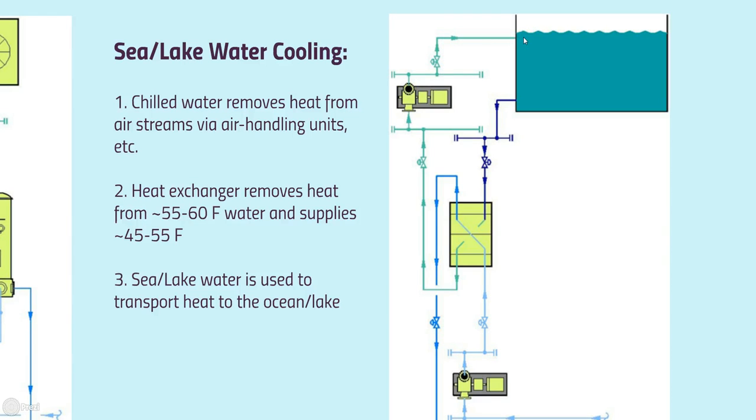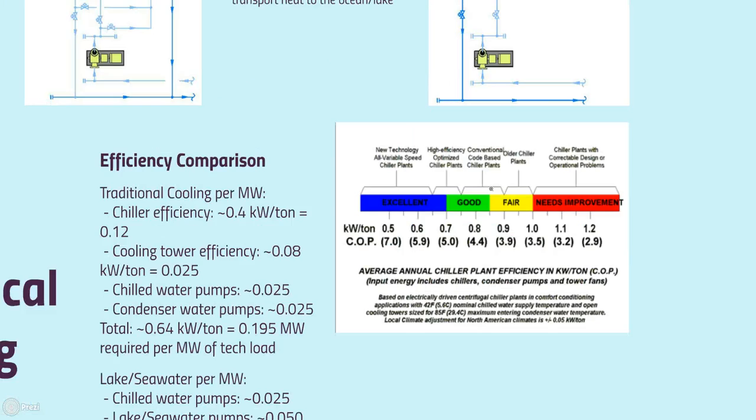Now, again, what we're looking at is about a 10 degree Fahrenheit temperature difference, about 5 degrees Celsius, using those rough numbers. Essentially, it's going through that cycle, single pass. There's no dual pass, but it's very easy, very predictable, and you can start to size both sides of the system based on the flow and the temperature changes. This is very, very simple, and not only that, it's really much easier to maintain.